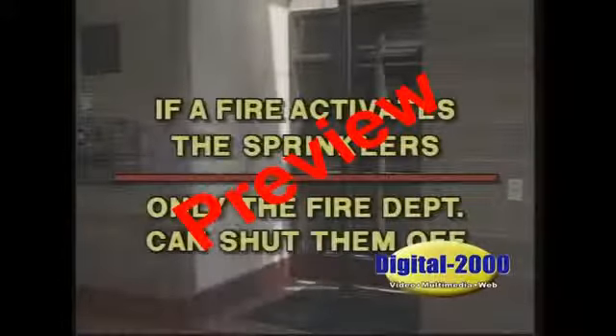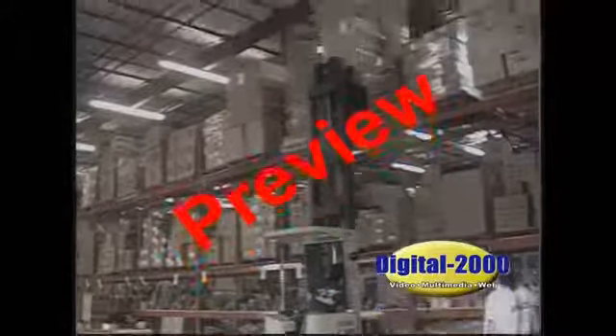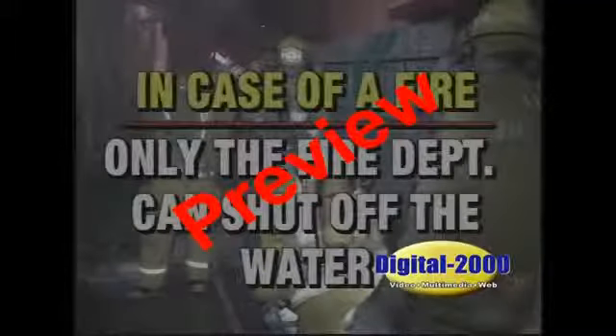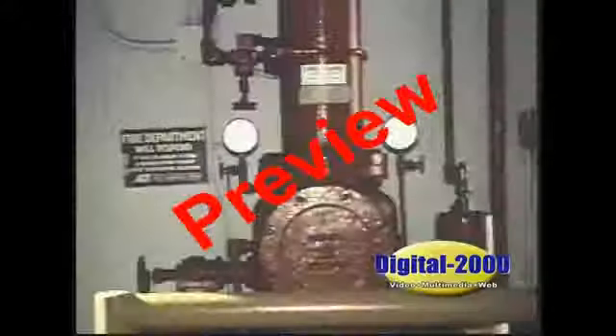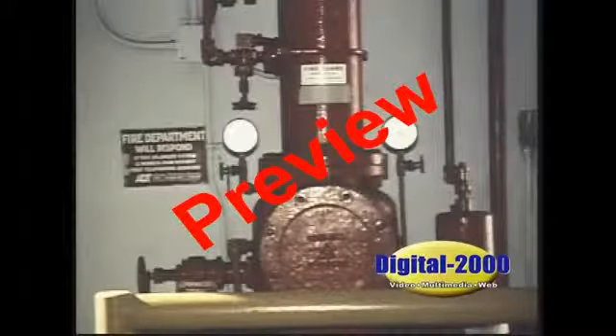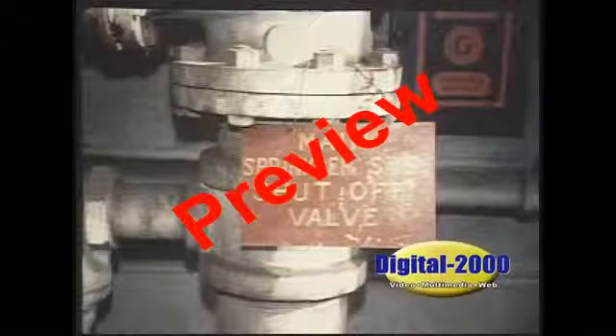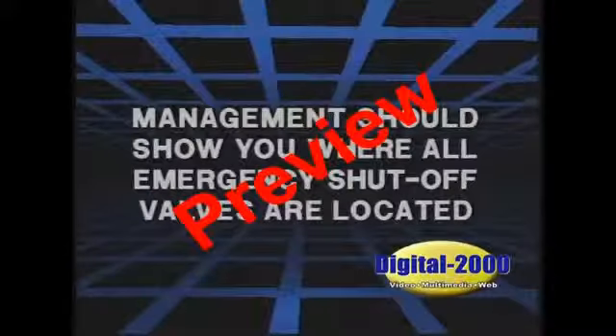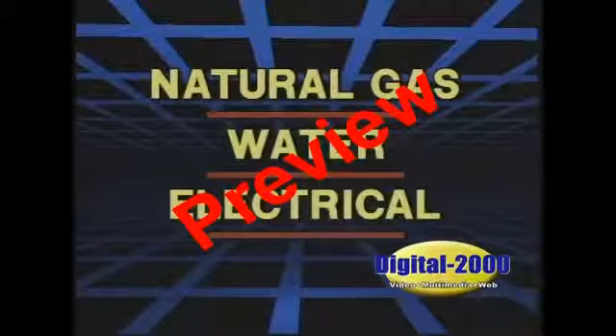If a fire activates the sprinklers, only the fire department can shut off the water. If a sprinkler head is broken off by a forklift or other accident, you can shut off the water to prevent excessive water damage. In case of a fire, only the fire department can shut off the water. The sprinkler shut-off valves are usually located inside the building, such as shown here. Or it may be located outside on a PIV or post indicator valve, as seen here. Management should make you aware where all emergency shutoffs are located: natural gas, water, electrical, and sprinkler systems.